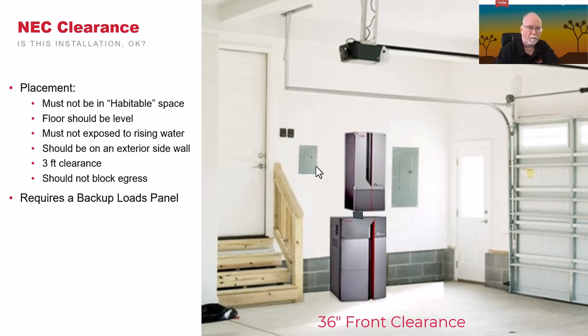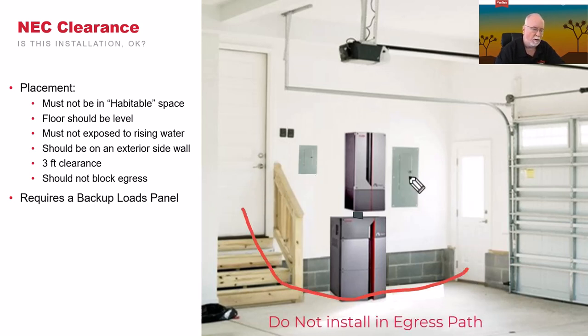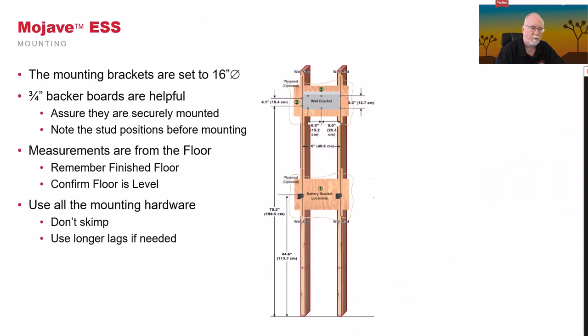loads panel. So again, this all looks good, but important things to remember per the NEC, you do not want to put this in an egress point. You do not want to put this on an inside wall, and you want to make sure that all the panels are spaced accordingly. So it's not a big deal, just something to note. So let's go ahead and take a look at the actual install.